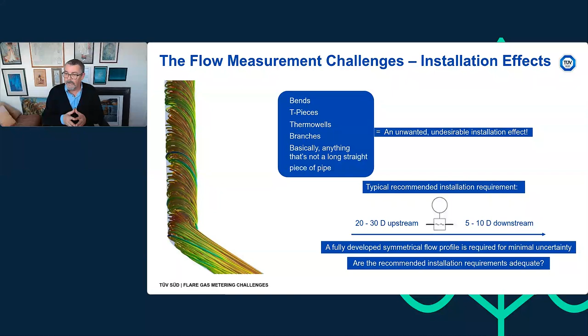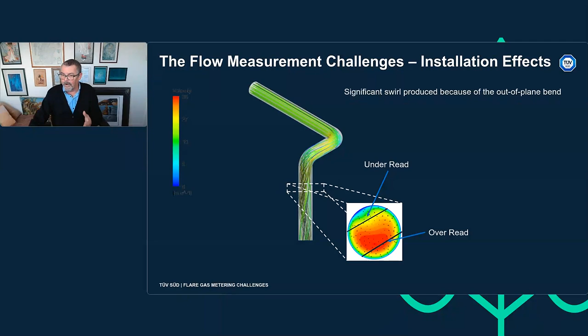Why is that an issue? Well, if we look at the example here of an out-of-plane bend, a relatively simple installation effect, we can see that depending on where I put my transducers for the ultrasonic meter, I could either overread significantly or underread significantly. And again, bear in mind we're trying to have no biases, no installation effects, and minimal uncertainty with a single path or a dual path meter.